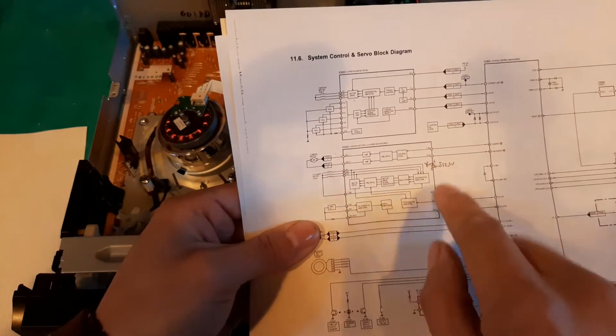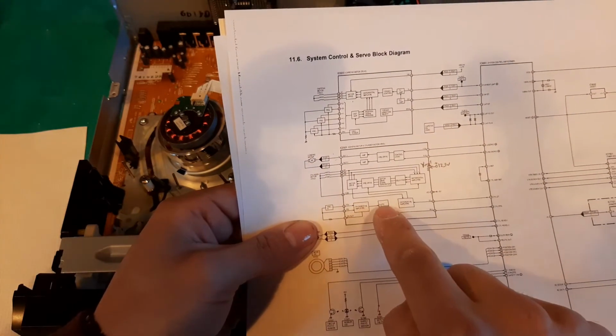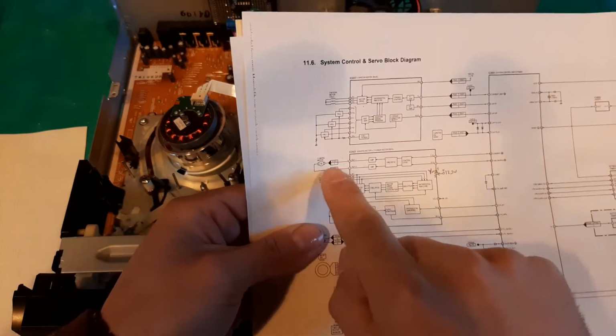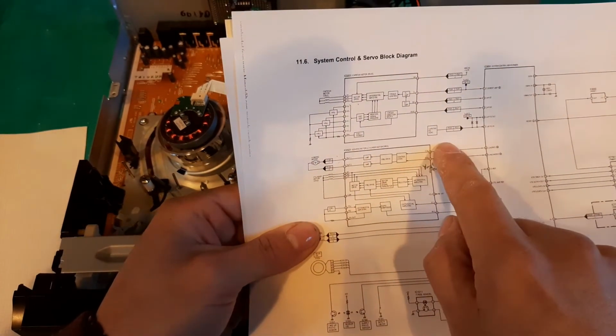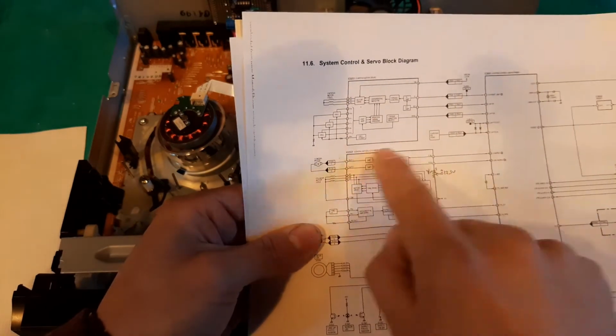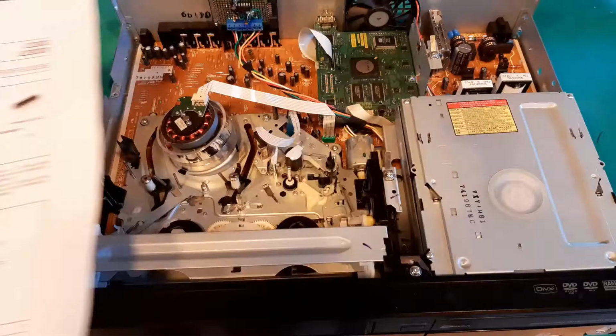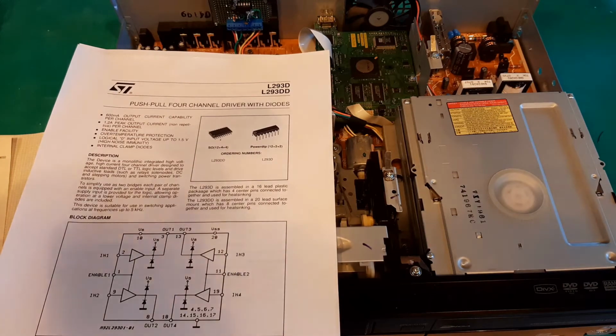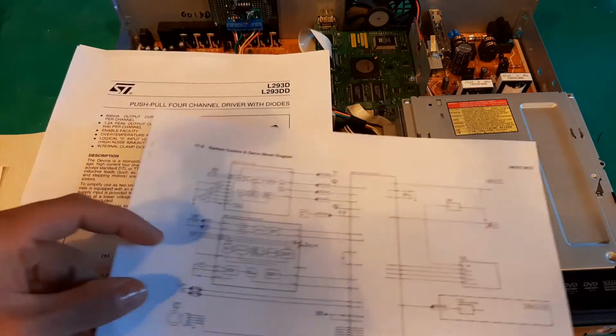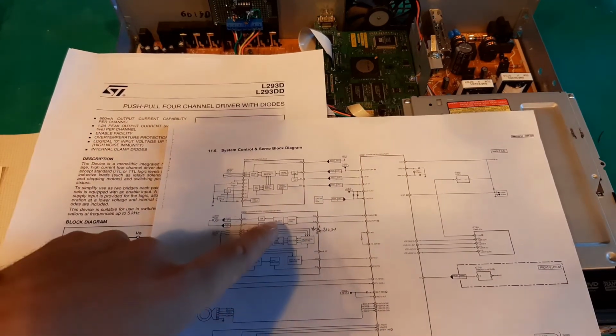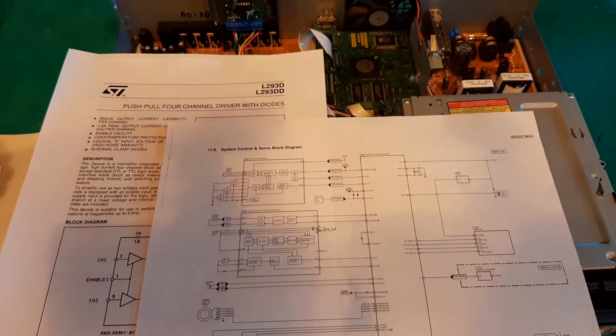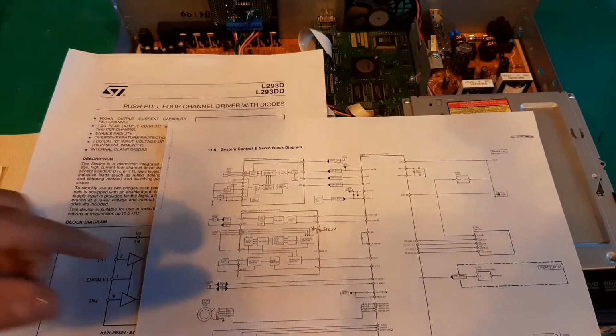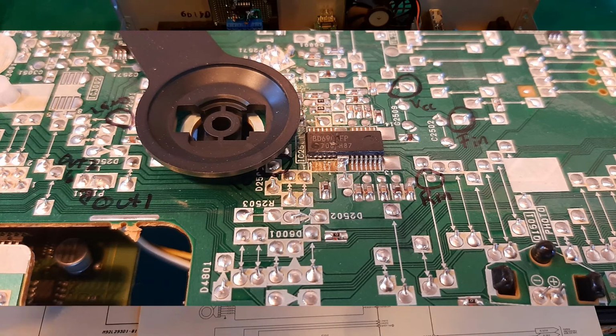That narrowed all the problems down to this chip here, because we had signals coming in and we knew our motor was fine, but the input signal was not getting to the motor, and this was the only thing in between. So to fix this, we would have to make a circuit that emulated the behavior of the top part of this chip, and then solder wires to the circuit board at the appropriate locations to tap into the loading signal, unloading signal, the voltage supply, ground, and the outputs to the motor.